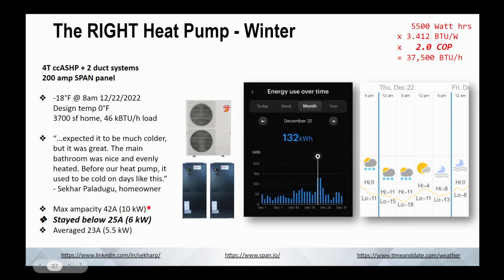It's 10 kWs. On this 25% beyond design temperature day, it stayed below 25 amps. It stayed below 6 kW. Not 10 kW, but 6 kW for that day. It heated the house, and it actually averaged, throughout the day, slightly lower than that. So this thing is cranking most of the day. It's operating at like 90% capacity for the entire day.